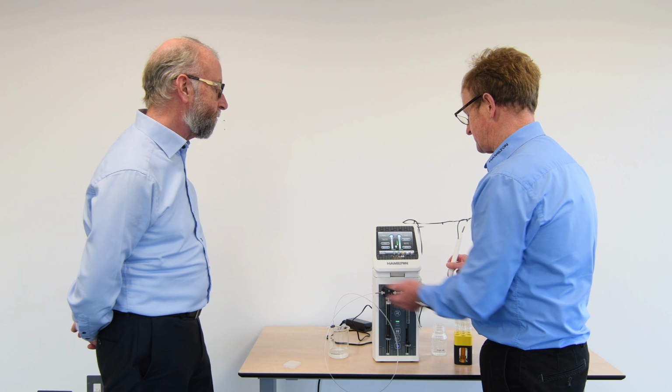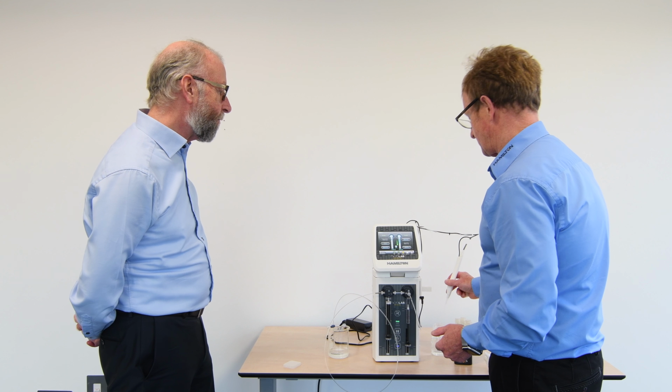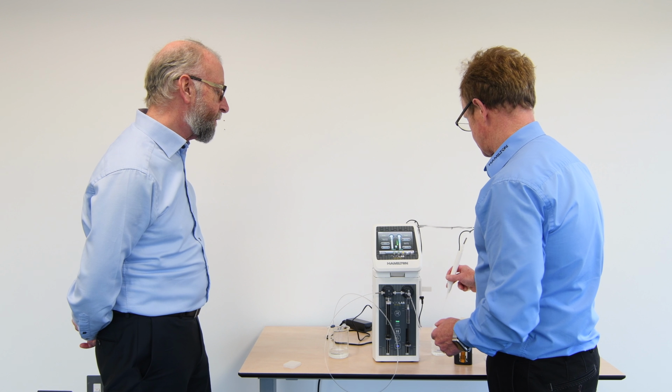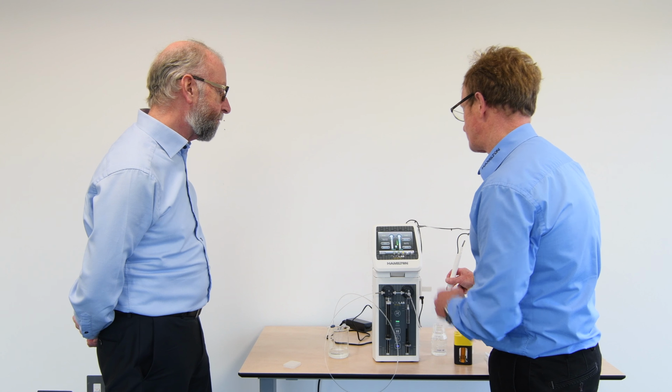So we've completed that wash cycle. Good. To show that whole cycle there, ready for the next program step. So there you are, Chris. We used the sample and the diluent volume to give you that 1 in 4 dilution, and we included the wash cycle at the end of that. I mean, that does cover much of what most people need to do.